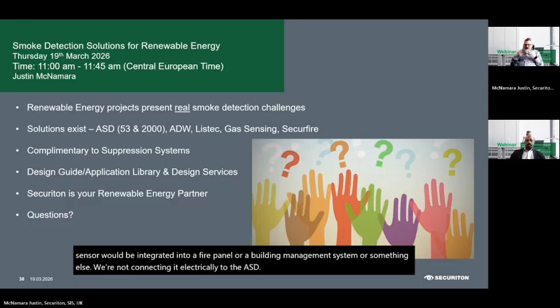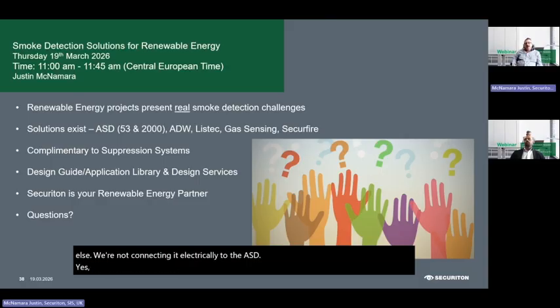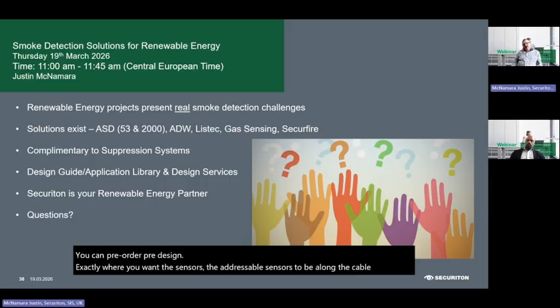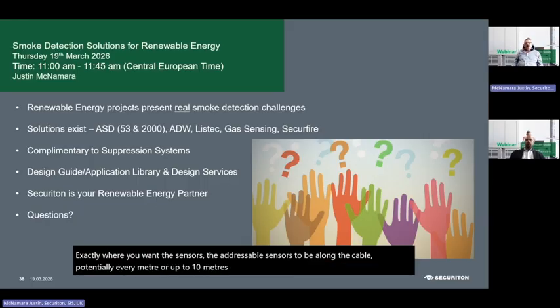And the last question: is your linear heat detection solution addressable? Yes, it is, I mentioned it a couple of times. You can pre-design exactly where you want the addressable sensors to be along the cable, potentially every meter or up to 10 meters - you can decide how often. There are standards we have to adhere to, but it's also possible to enhance those standards and have addressable sensors more frequently than required under the regulations. But yes, it is very addressable.